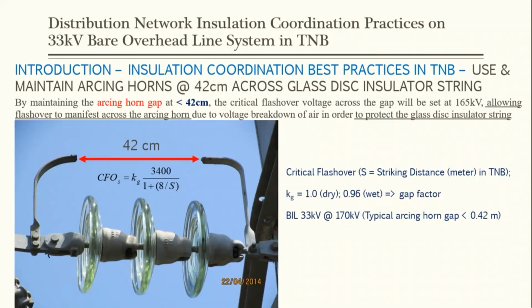number 4, we use and maintain the arcing horns at 42 cm across glass insulator string. Okay, a lot of questions came by or were directed to us. Why 42 centimeters? Why not 50? Why not 30? Why even install the arcing horns, when it only does this, causing transient tripping, right? So by maintaining the arcing horn gap at less than 42 cm, the critical flashover voltage across the gap will be set at 165 kV, allowing flashover to manifest across the arcing horns due to voltage breakdown of air in order to protect the glass disc insulator string.